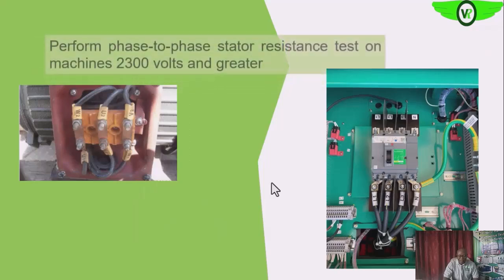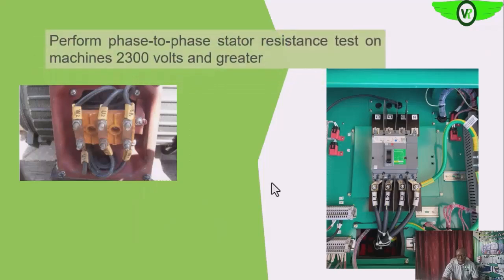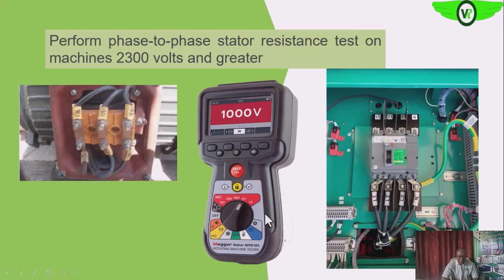So the next test you want to carry out is the resistance test. Since the windings, the U, V and W windings, are made of the same materials, the same wire size, the same number of turns, it is expected that the resistances of the three windings will be the same. If you have your milliohm resistance meter, you turn the selection switch to the milliohm test range, okay? And then you probe. If it is the U phase, this is U1, U2. After disconnecting it, you probe between U1 and U2. It will give you a resistance level, you register it.